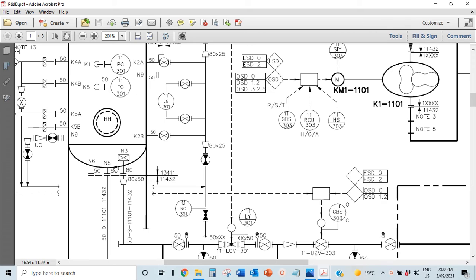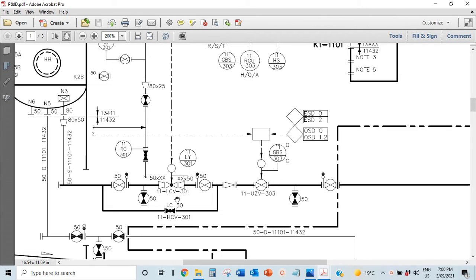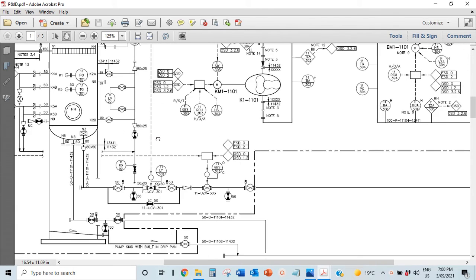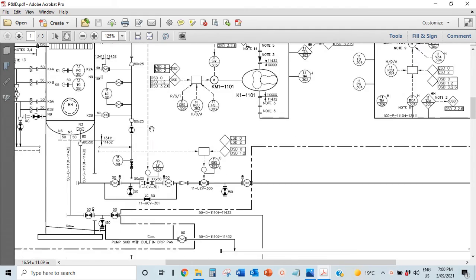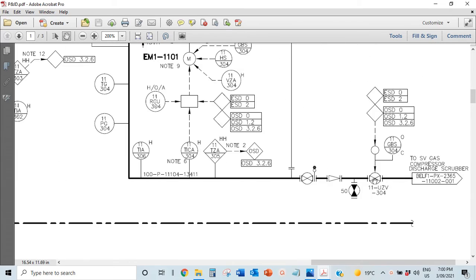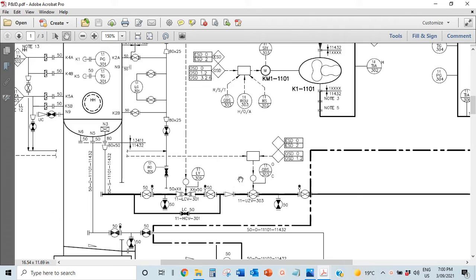That means the gas can force its way into the liquid leg, which is really bad because the systems on the liquid side are not rated for high pressure. So you have these shutdown valves, well, let me not say everywhere. You have some philosophy to guide you.